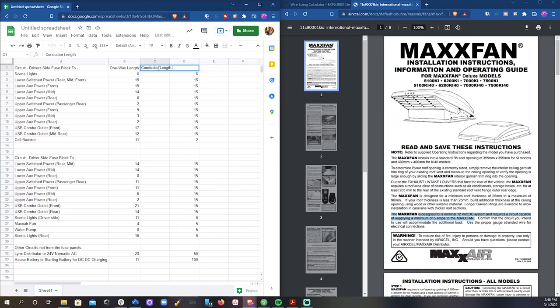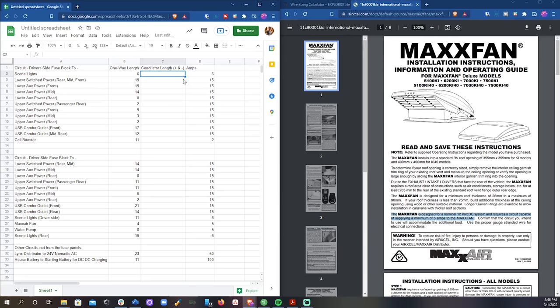The lengths of wire runs in the 12-volt DC circuits matters quite a bit. The longer the run, the bigger the wire needs to be, so the length of both the positive and negative wires needs to be accounted for. So I just multiplied everything on the one-way length column by two to get the total length of the conductors in each circuit.